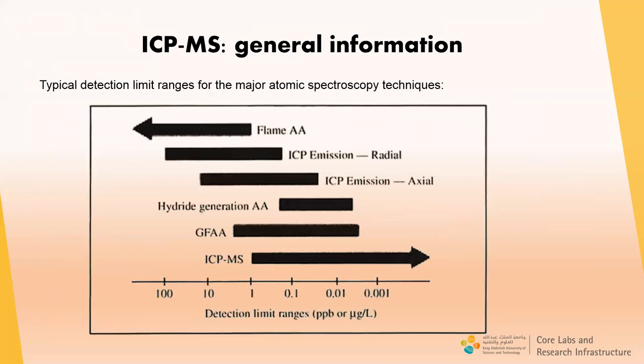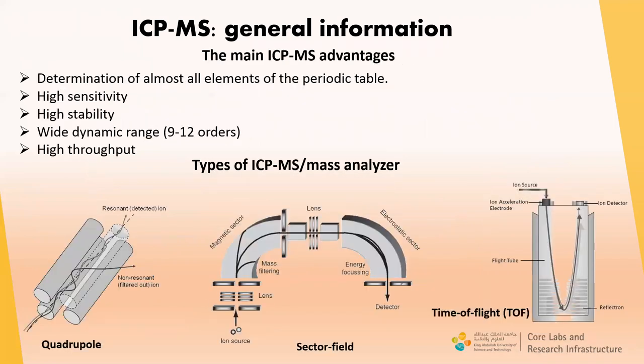Currently, the ICP-MS method is the most sensitive among the major atomic spectroscopy techniques. Detection limits achieve concentrations less than nanogram per liter, which is significantly better than the previously more sensitive method — atomic absorption with graphite furnace — can offer. Except for high sensitivity, ICP-MS provides the following advantages: determination of almost all elements of the periodic table, high stability, wide dynamic range, and high throughput. At the present time, the ICP-MS method is very popular and widely used in analytical laboratories.